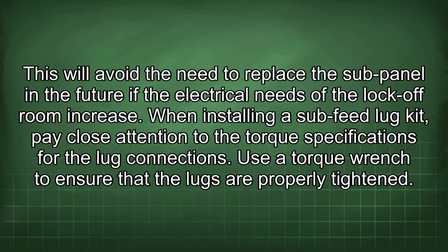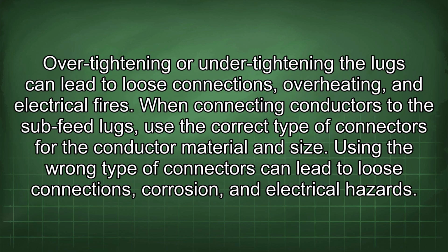Use a torque wrench to ensure that the lugs are properly tightened. Over-tightening or under-tightening the lugs can lead to loose connections, overheating, and electrical fires. When connecting conductors to the sub-feed lugs, use the correct type of connectors for the conductor material and size. Using the wrong type of connectors can lead to loose connections, corrosion, and electrical hazards.